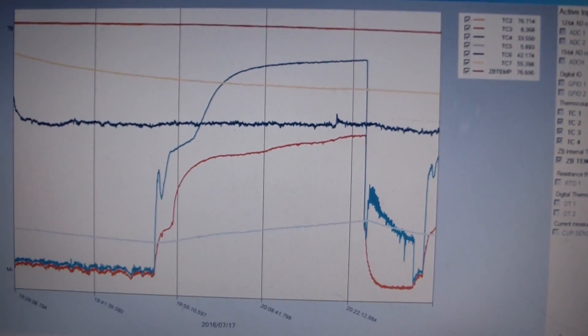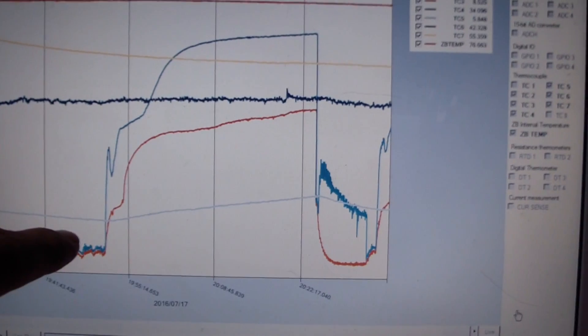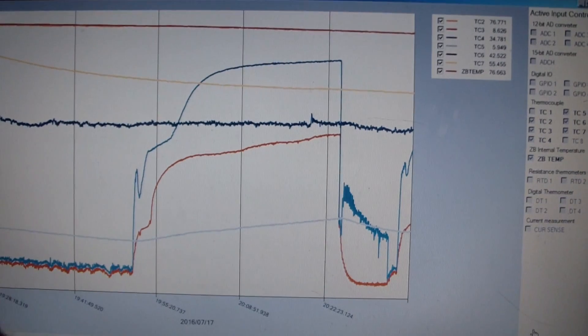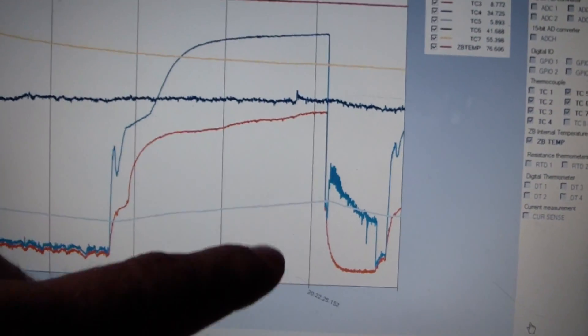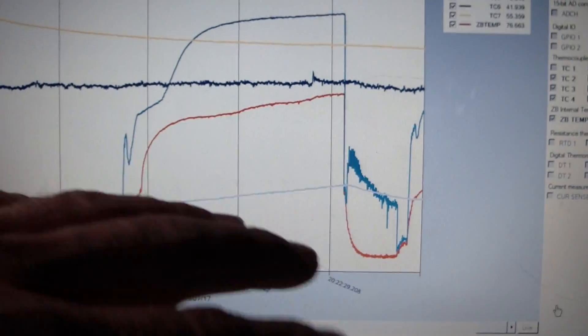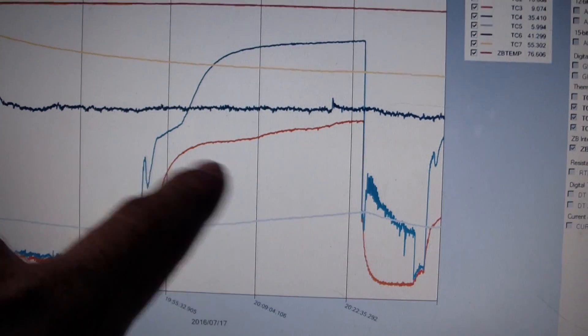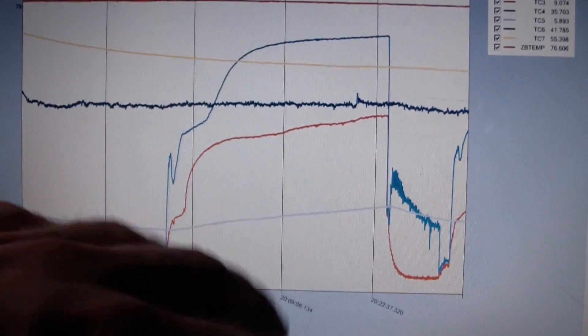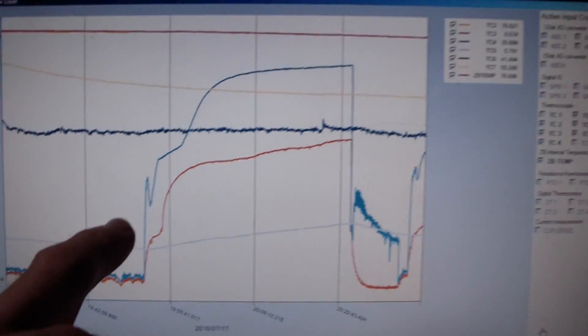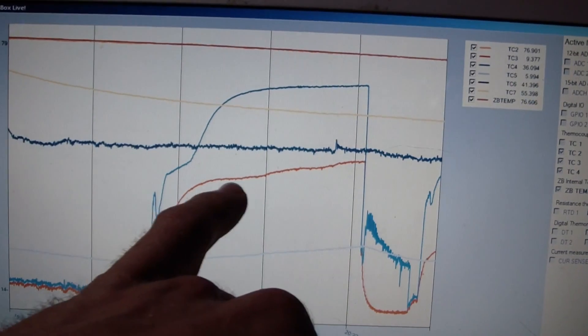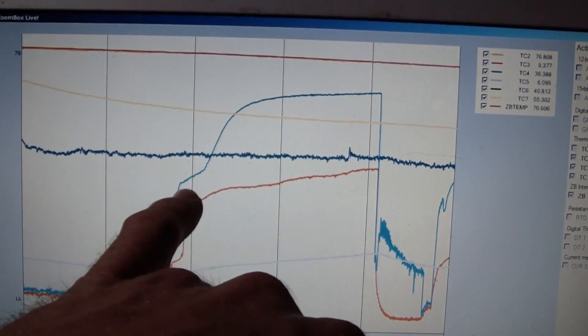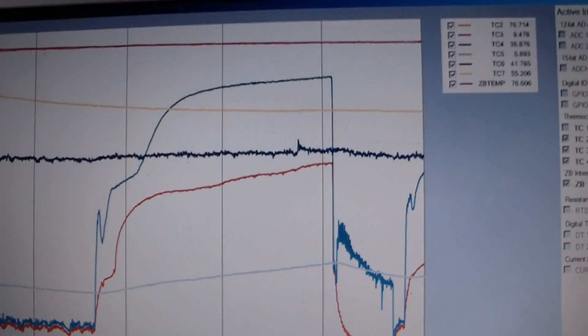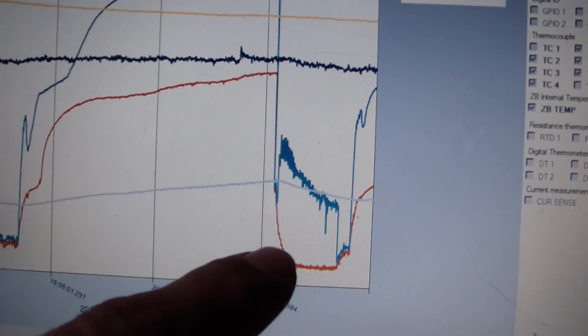Beyond that, this light blue and the red there, those are the two suction superheat values. I just recently adjusted the temperature the thermostat operates at because I was running about 5 to 15 degrees Fahrenheit and the air temperature is dropping pretty rapidly. So I'm going to go ahead and run it probably tonight between 10 and 20. You can see the red one that rises. That's actually in the cabinet there, so it doesn't rise as rapidly to its high temperature, stays pretty much below the air temperature or right about it. Then the blue one is exposed to ambient air up here so it's going to warm up a little bit.